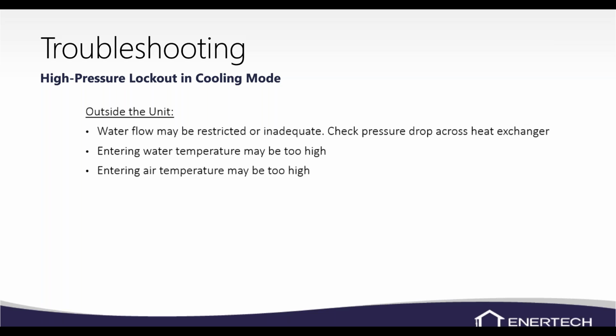You could have entering air temperature too high on your return air. Maybe you're pulling outside air. I know I ran into this problem out in Texas, not last August, the August before, and they were pulling a bunch of fresh air in and really overloading the unit. I mean, it was 110 degrees outside, so they're really having too high return air temperatures.